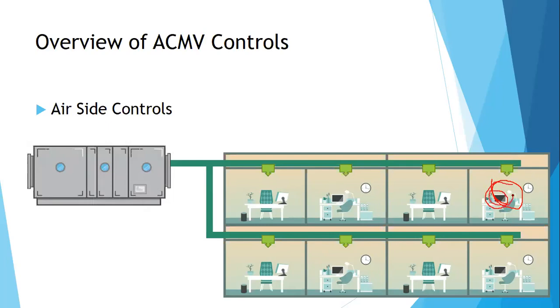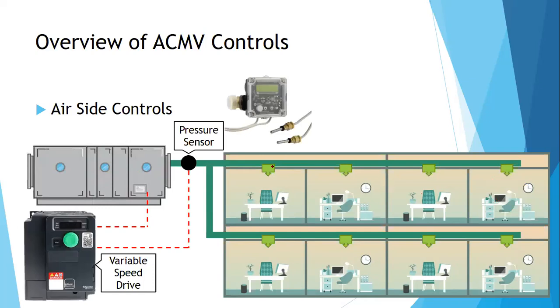Example, this guy that sits here tends to work very less, goes home early. So this guy will turn off his aircon. So what is this unit going to do? So this unit is sending out 10, 20, 30, 40, 50, 60, 70, 80. So there's eight rooms, 10 cmh each. So assuming that this air conditioning unit is sending out 80 cubic meter per hour of air to all rooms, except for this one. How is this aircon going to know that it needs to go up or go down, or ramp up or ramp down, or speed up or speed down? Okay. So first of the airside controls is the pressure sensor. So this pressure sensor monitors the pressure within your main duct system.